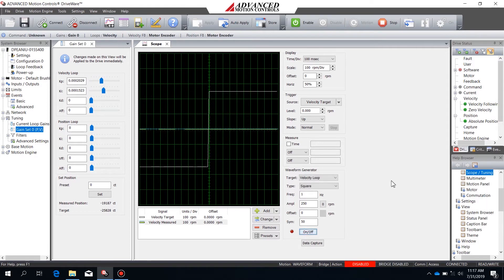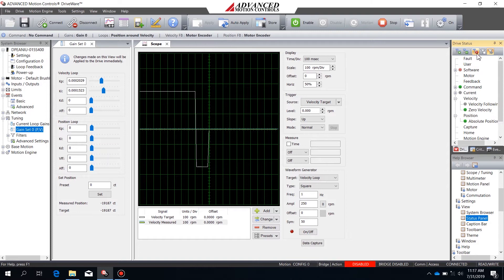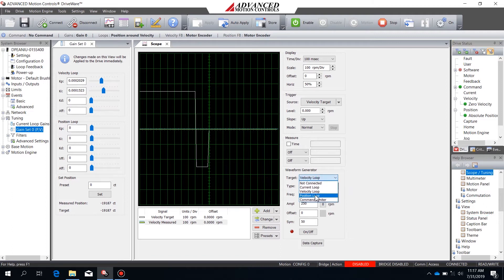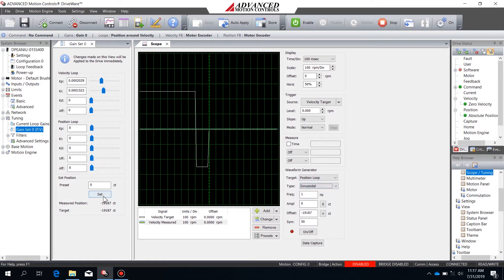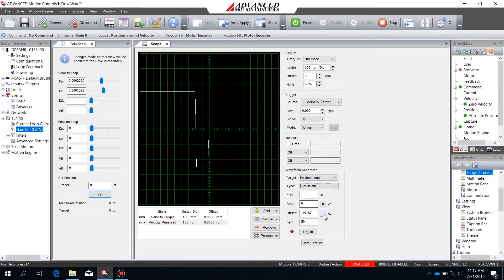I've disabled the bridge and I'm going to disable the waveform generator so I can begin position loop tuning. To start that process I'll change the target to position loop, the type to sine wave, and keep the frequency at 1 Hz. I'm going to reconfigure the set position to clear its current position and then clear the offset to ensure the wave is centered around zero. I'll set the amplitude to about 2500 counts, which in my case is a quarter revolution, and then set my presets to position loop.